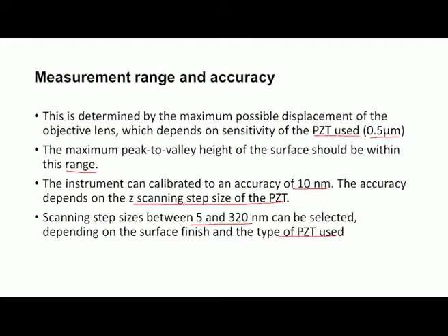So, what is the resolution of this setup? The vertical resolution depends on the sensitivity of the PZT that is used. Vertical resolutions of 5 and 40 nanometer are possible with PZTs of sensitivities 5 micrometer per 1000 volt and 40 micrometer per 1000 volt respectively. So, if we use a PZT with sensitivity of 5 micron per 1000 volt, then the vertical resolution, that means the least value by which the objective lens can be moved, will be 5 nanometer.